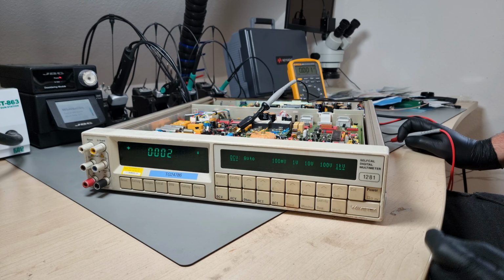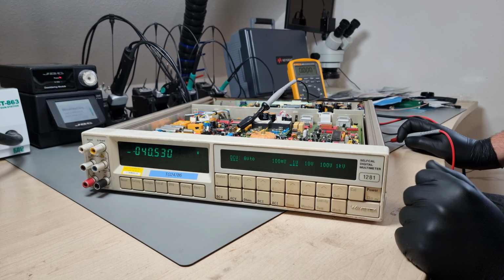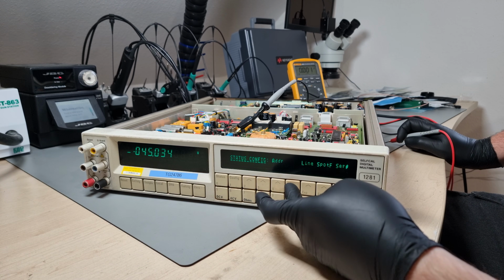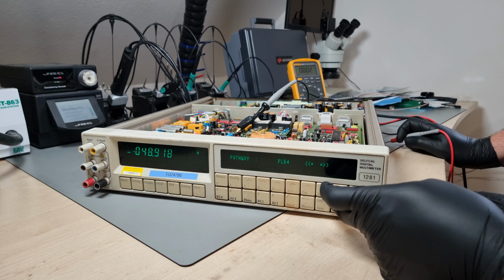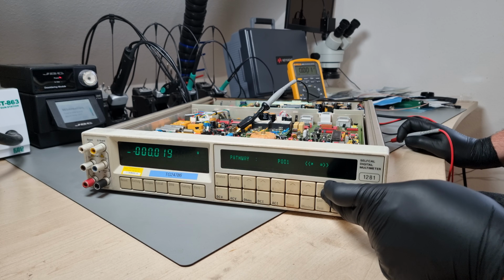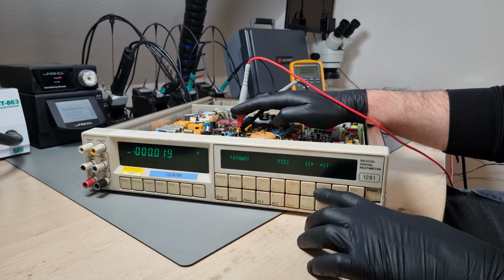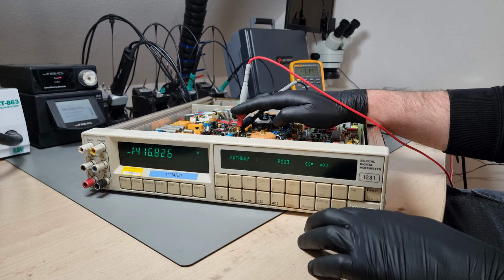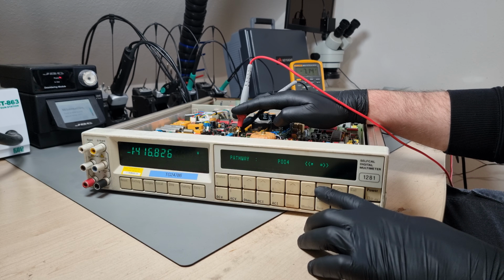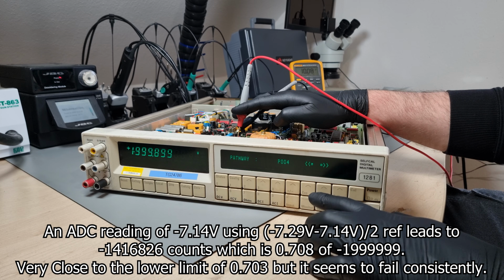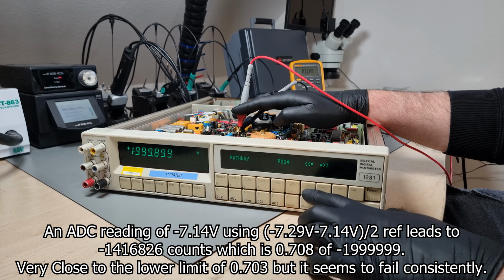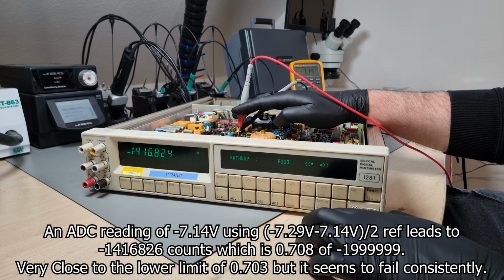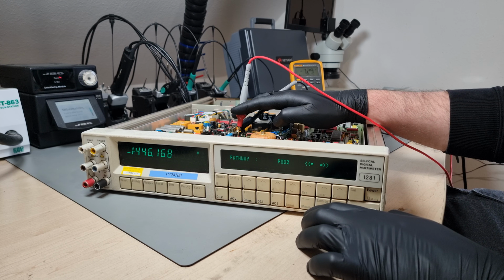As always, we can enter the self-test configurations manually and probe the circuitry while observing what the ADC is putting out on the meter's own display. A full-scale reading is 1.999999, or let's say 2, so that I don't have to speak so much German, whenever it sees a 10-volt input. So when seeing the healthy, normal -7.14 output from voltage reference module 2, the ADC reading seems reasonable to me. Now the other Vref module seems to be putting out 7.3 almost.